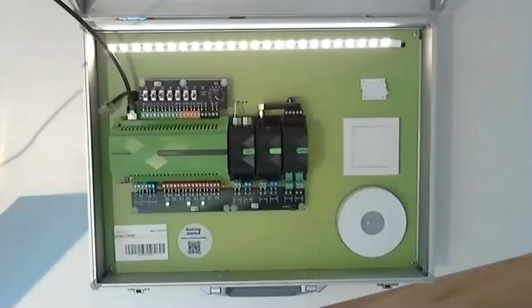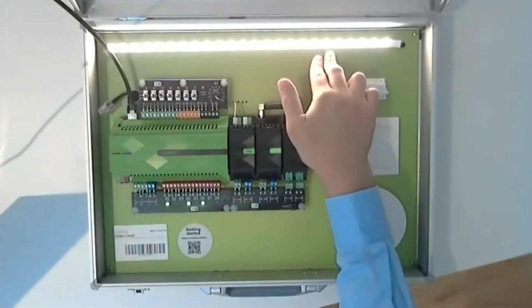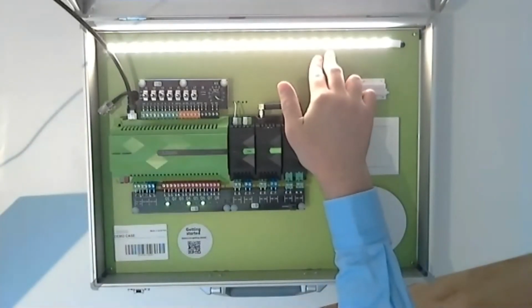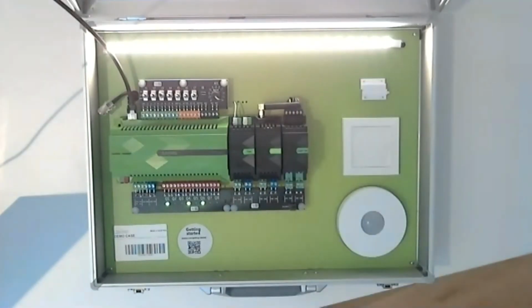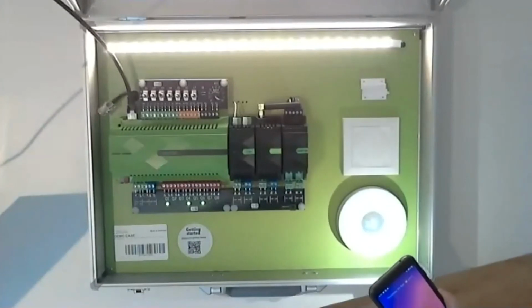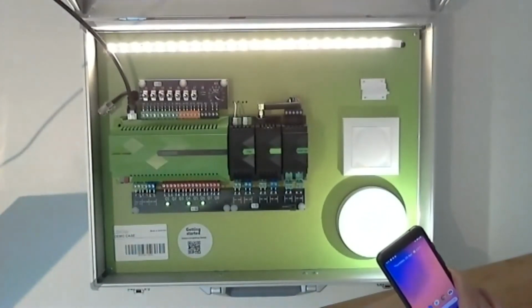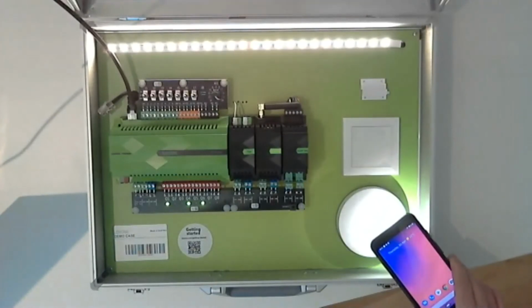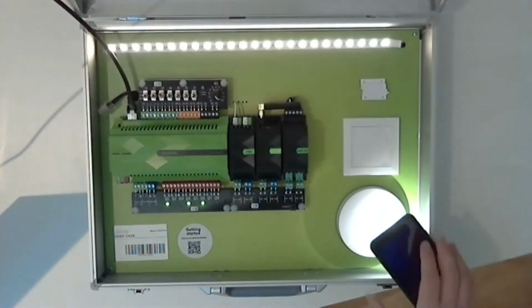If I just stop showing my screen to show you this properly, so you can see there, this is at the moment dimming up. It's dimming up because we are well under our desired brightness. I'm only at about 161 lux. Again, start increasing the brightness level. And you'll see there, you'll start to see that the LED strip is dimming itself down. So you can see it's a nice gradual fade between dim up, dim down.